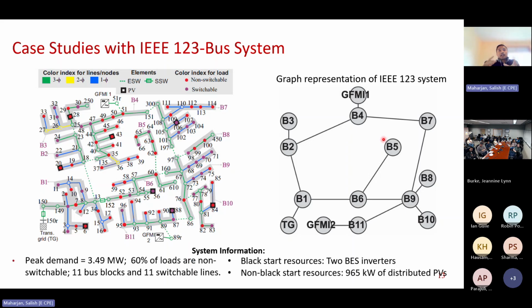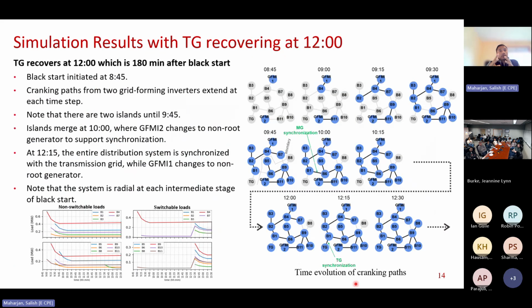Okay, and then the graph representation is shown here. And it has two blackstart resources, which are basically two BES-based grid forming inverters. And it also has 965 kilowatt of distributed PVs, which are basically non-blackstart resources. So when we run the algorithm, it gives you the sequence of the switching for the blackstart. And the scenario, we have considered a scenario here. So our black start initiates at 8:45 a.m., right? And the transmission grid recovers at 12, which is 180 minutes after the black start initiation.